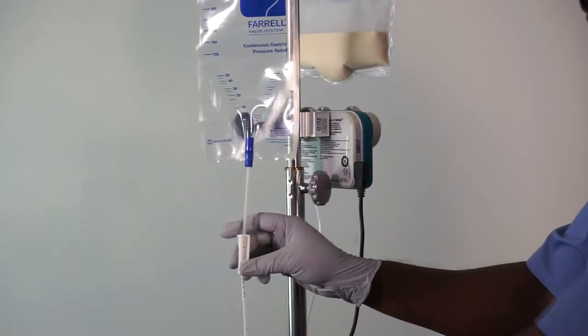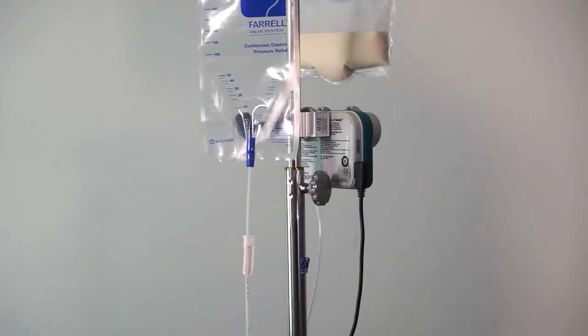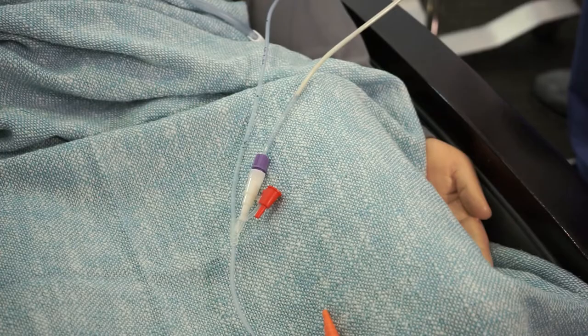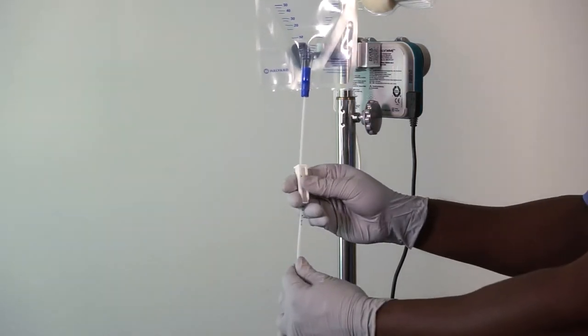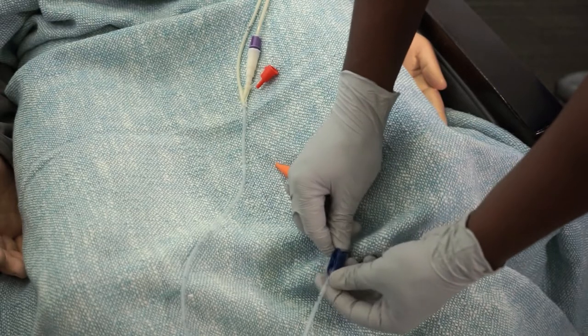Open the white roller clamp and prime the giving set. With the pump in operation, allow the feed to travel a short distance up the line towards the Farrell bag. Close the white roller clamp, open the blue clamp, and continue to prime the giving set.